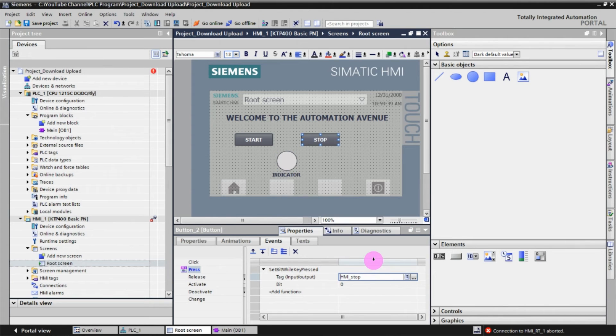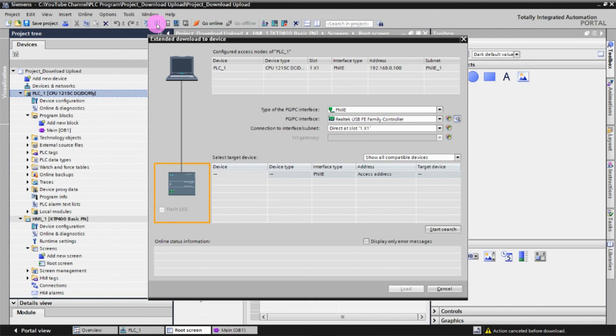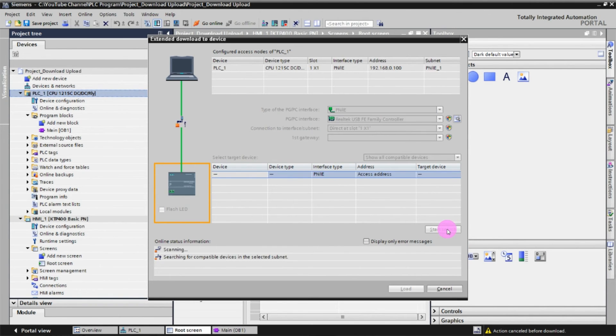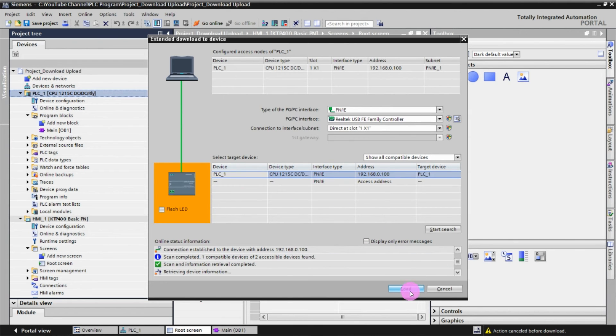We have linked the PLC tags to the HMI buttons. Now we can download the PLC program first, then the HMI program. Click on the PLC, click the Download to Device button, then select Start Search, select the real PLC, and click Load.